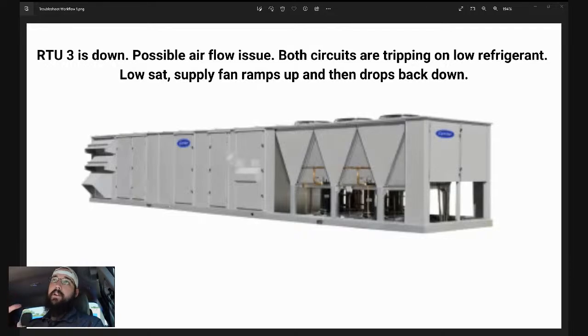And so with the constant airstream, he'd be able to get hopefully more stable readings. So I have a little bit of feedback with that. As he was staging it up, he went one compressor by itself, then he brought in a second compressor, let them both run together on circuit 1. Then he did the same test on circuit 2. And the final diagnosis, he's recommending that maybe the TXV be replaced on circuit 1 because of the heavy fluctuations.